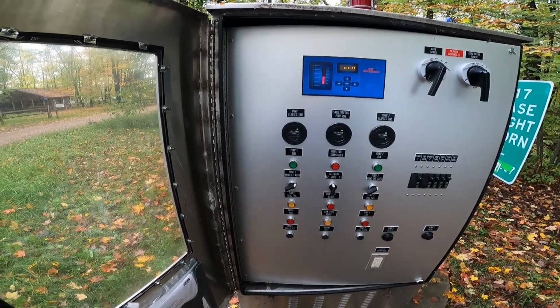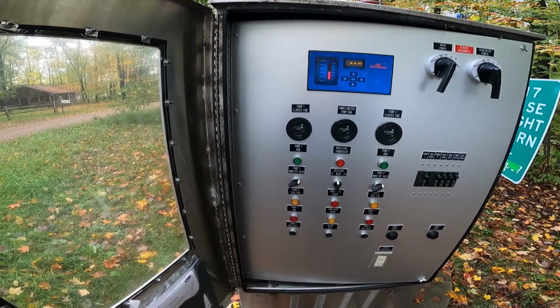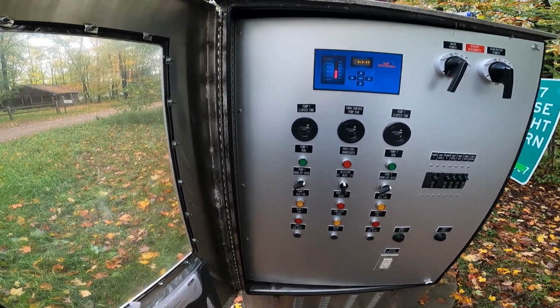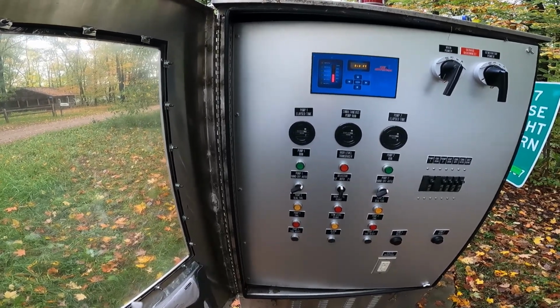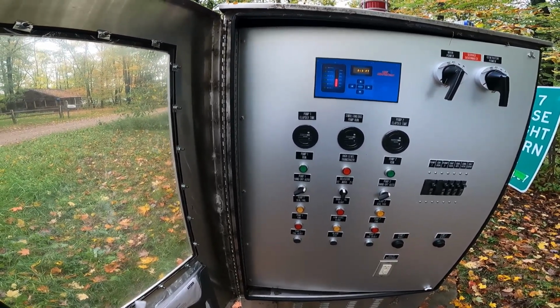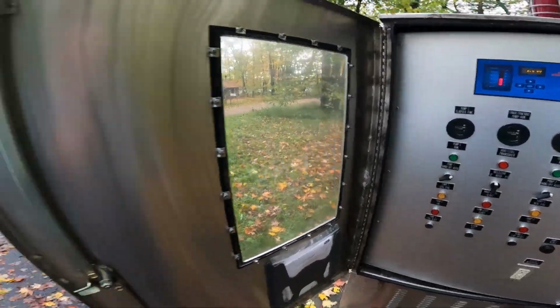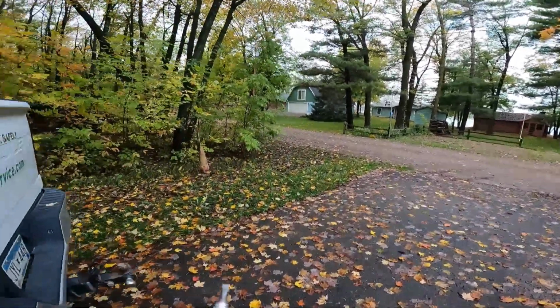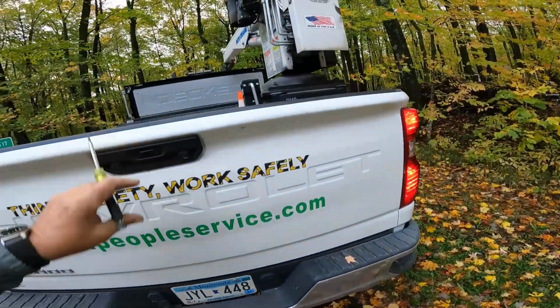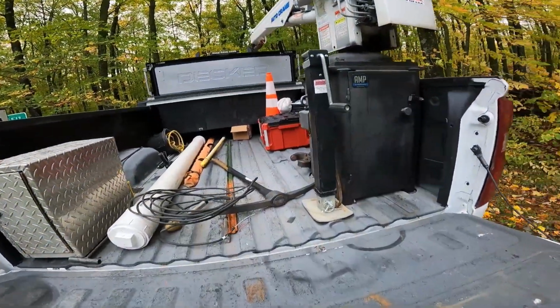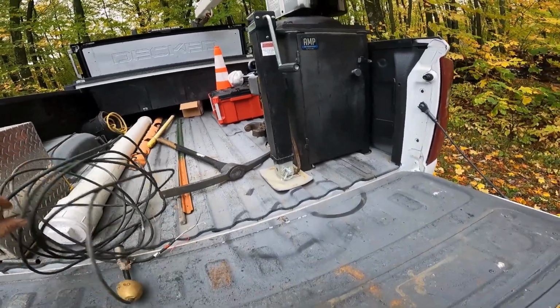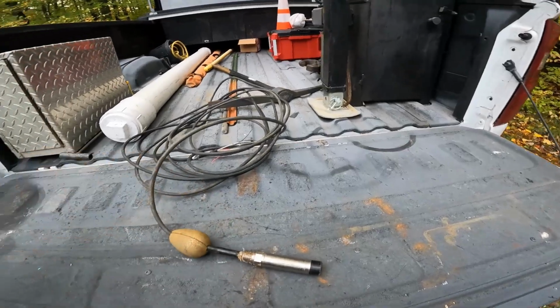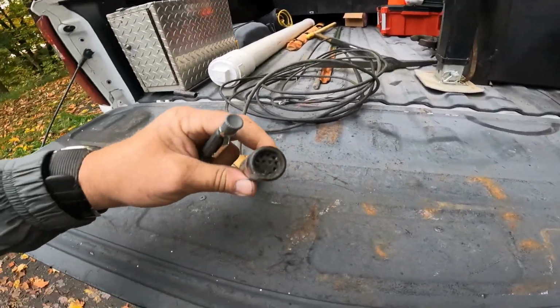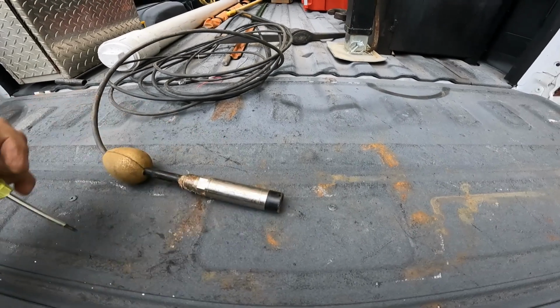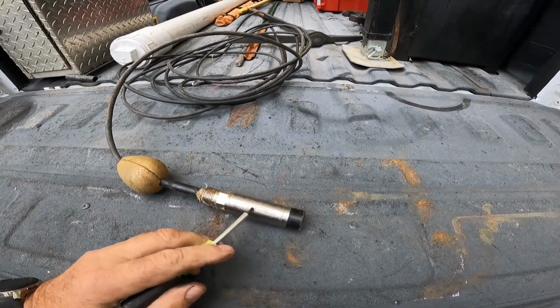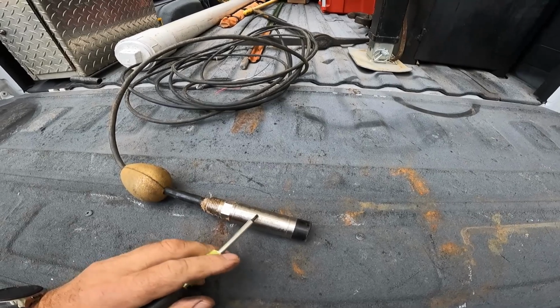So if this holds steady, then we know we've made the repair to what was just a bad ground. If not, then we know that we've got to put on a different transducer. So let's go look in the back of the truck, because I have a temporary transducer, and that's what this is. This is a transducer that goes in the tank, and it's a pressure transducer, and this is a 0 to 10 psi transducer for this smaller station.